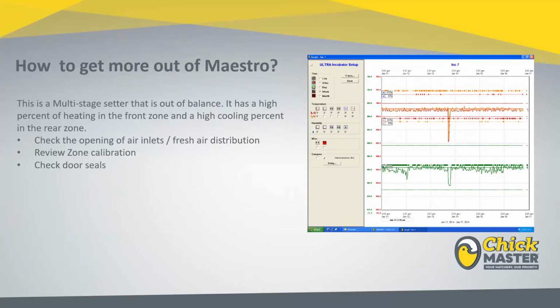When we look at multi-stage, now that we've talked quite a bit about single stage, there are several opportunities to focus on. One being, in this particular case, we have a multi-stage setter that is out of balance. And I say that because it has a high percentage of heating in the front zone and a high cooling percent in the rear zone. So essentially the front's doing all the heating and the rear's doing all the cooling, so it's referred to as a machine that's out of balance.